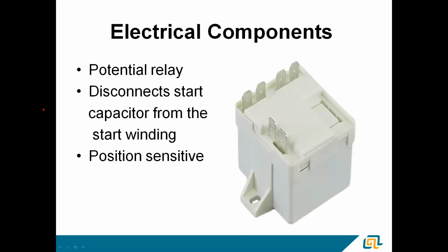Potential relay disconnects the start winding from the capacitor. They are position sensitive. There are contacts inside of there that, if you put this thing in the wrong orientation, the contacts will either never open or never close. So gotta keep an eye on it. A lot of times there'll be an arrow on them, up or something like that. So just so you're aware, they are position sensitive.